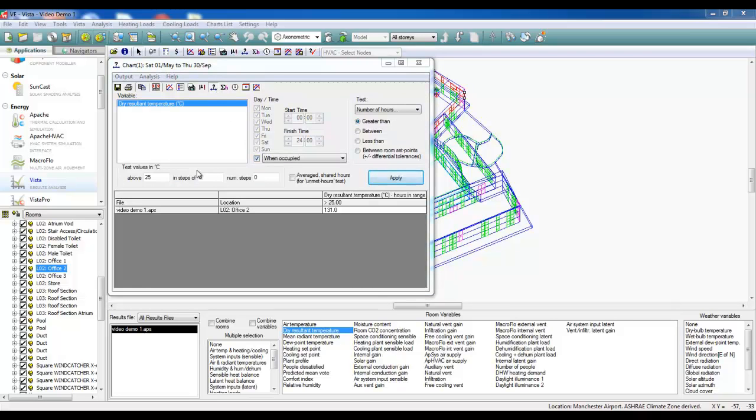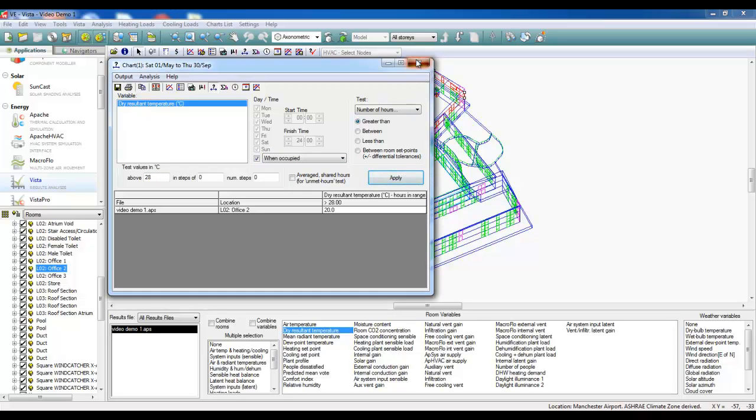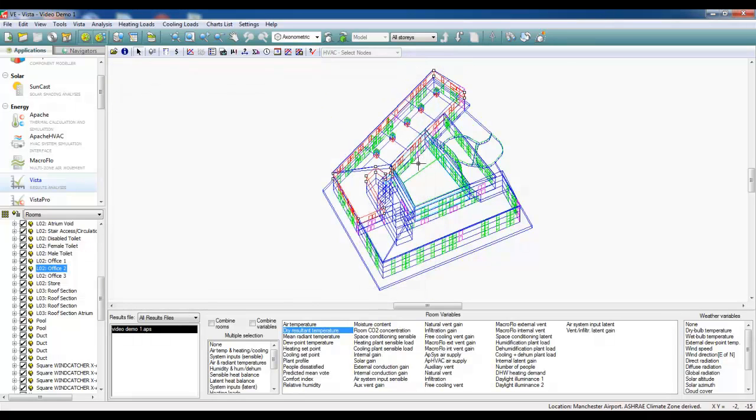We can also look at how many hours are exceeding 28 degrees to ensure that we've got CIBSE Guide A compliance. We can see that there's no more than 20 hours exceeding 28 degrees, which means that we will comply with the CIBSE criteria for naturally ventilated buildings.